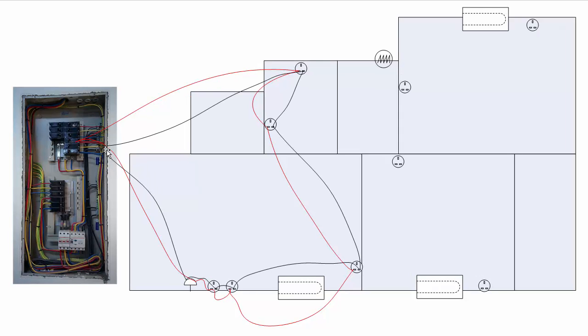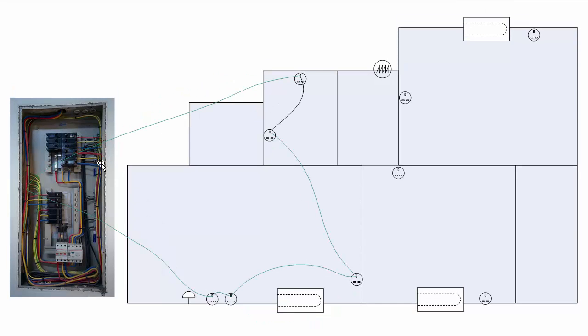Similarly we complete the neutral wire connection in the same ring fashion — the neutral wire is also connected in a ring, terminating back at the starting point on the neutral bar. Similarly we complete the earth wire, taking it from one terminal and forming a ring. In this particular case the bell does not need an earth wire, but if it does, that must be connected too.